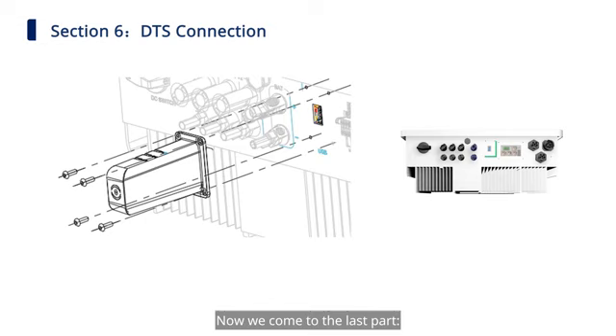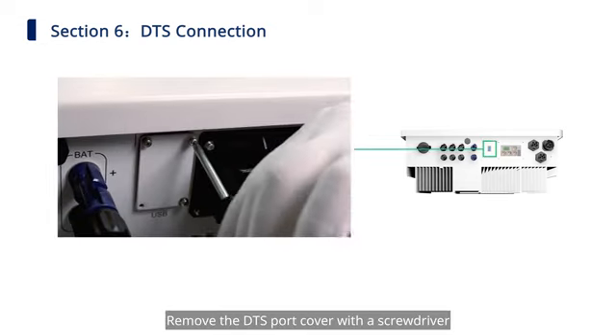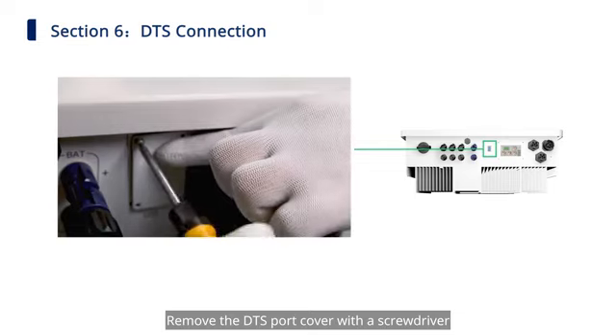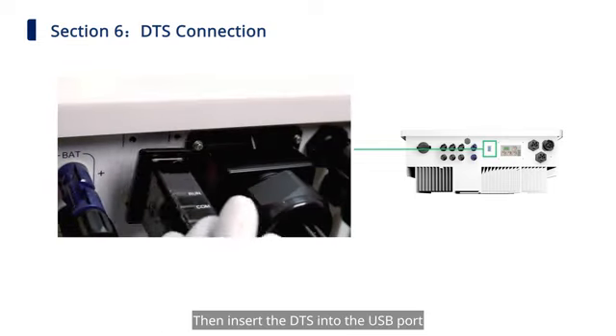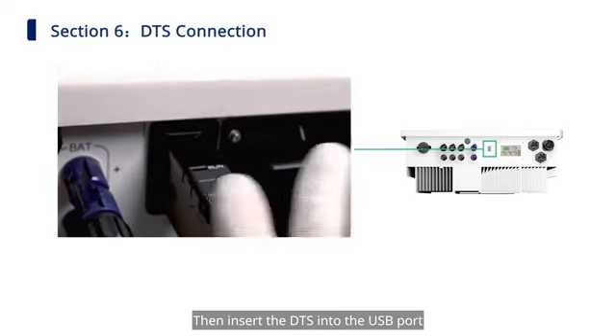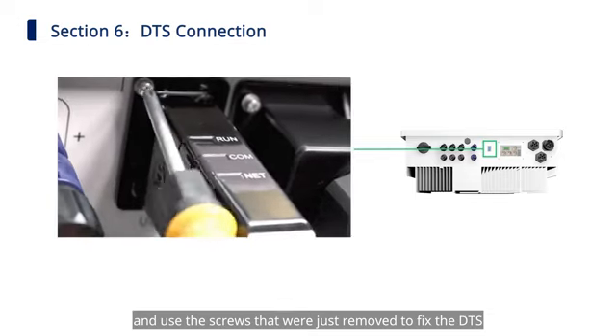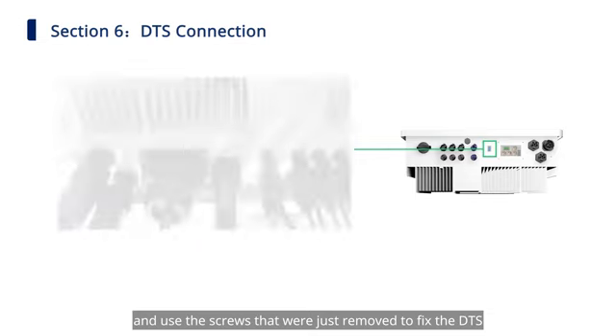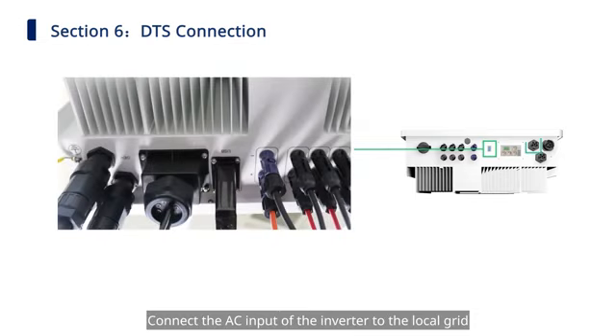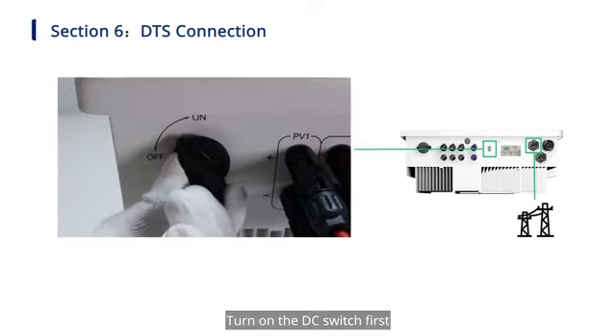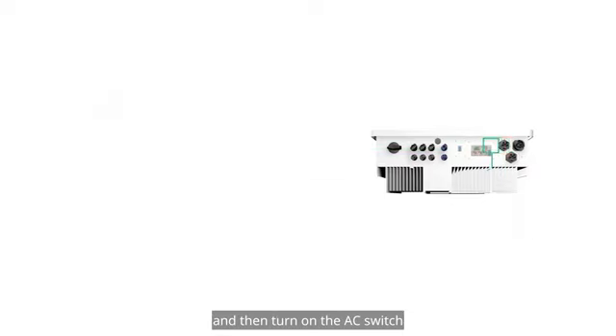Now, we come to the last part, the connection of DTS. Remove the DTS port cover with a screwdriver. Then insert the DTS into the USB port and use the screws that were just removed to fix the DTS. Connect the AC input of the inverter to the local grid to complete the installation of the hybrid inverter. Turn on the DC switch first, and then turn on the AC switch.